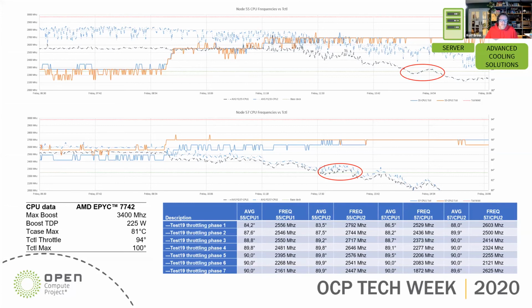And this is what some of these tests look like. What you're seeing here is tests with specific cooling inlet temperatures. This is one of the overheating tests that we do on purpose, so this has to be part of that test process where you're going to investigate: okay, so what really is that throttling temperature? If I have this assembly, this optimized system, what do I need to do? What kind of temperatures do I need to feed it before it starts impacting the performance of this platform?